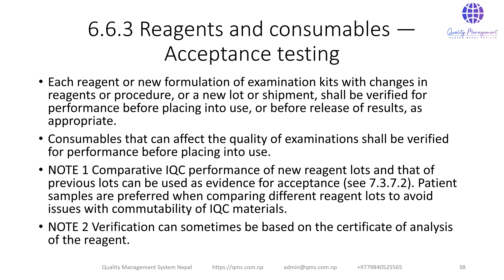6.6.3 Reagents and Consumables Acceptance Testing: Each reagent, new formulation of examination kits with changes in reagent or procedures, or new lot or shipment shall be verified for performance before placing into use or before release of results, as appropriate. Consumables that can affect the quality of examinations shall also be verified before use. Note 1: Comparative IQC performance of new reagent lots against previous lots can be used as evidence for acceptance. Patient samples are preferred when comparing different reagent lots to avoid commutability issues with IQC materials. Note 2: Verification can sometimes be based on the certificate of analysis of the reagent.